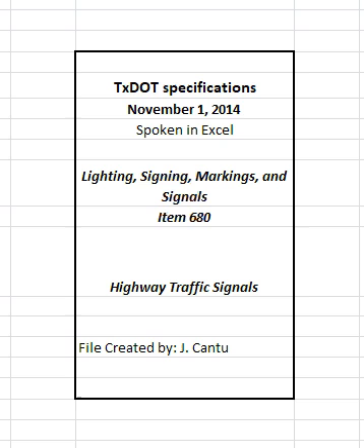Connect the equipment ground to all metal conduit, signal poles, controller housing, electrical service ground, ground rods, and all other metal enclosures and raceways. Provide copper wire bonding jumpers that are a minimum number 8 AWG.